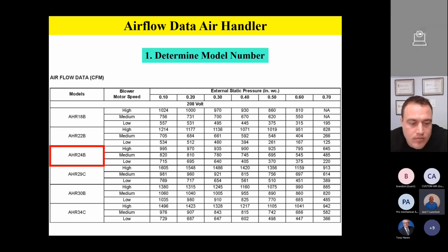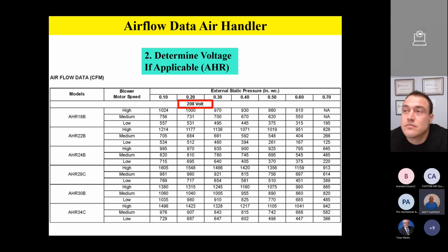So first, step number one, we take a look at our chart and we determine which model of air handler we're measuring the airflow on. So we look at the data plate and see what air handler we're dealing with. Step number two, if applicable. Now, some air handlers, if they're a capacitor style air handler, there's actually going to be two charts. There will be a 208 volt chart and a 230 volt chart. So if it's applicable, your manufacturer may or may not do this, but we do on our capacitor style air handlers or older style air handlers. If your voltage is closer to 208, you use a 208 volt chart. If it's closer to 230 volt, then you use a 230 volt chart. It'll make a slight difference in the amount of airflow that you're actually seeing. So determine voltage if applicable on your airflow chart.